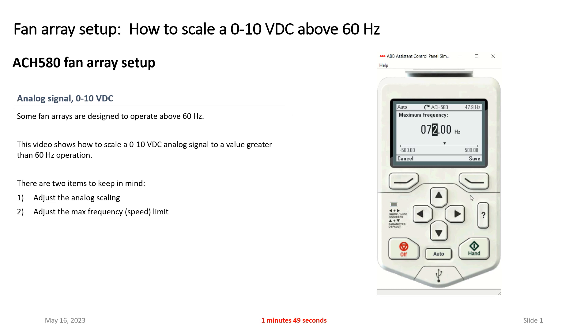So I've changed my analog scaling. I've changed the limit on the drive. And there you go. This drive will now give you 0 to 72 hertz when you have a 0 to 10 volt input.